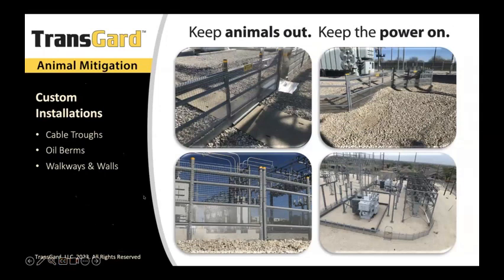So walkways and walls as well. In certain instances, we can terminate our fence up against the control buildings or anything like that and still have active protection across it. One of the things I note in the picture up in the right-hand section is we tend to design the fence to be in a zigzag formation around the protected equipment, and that's to help with wind loading. When we do that, it actually stabilizes the fence and helps it become more resistant to wind.